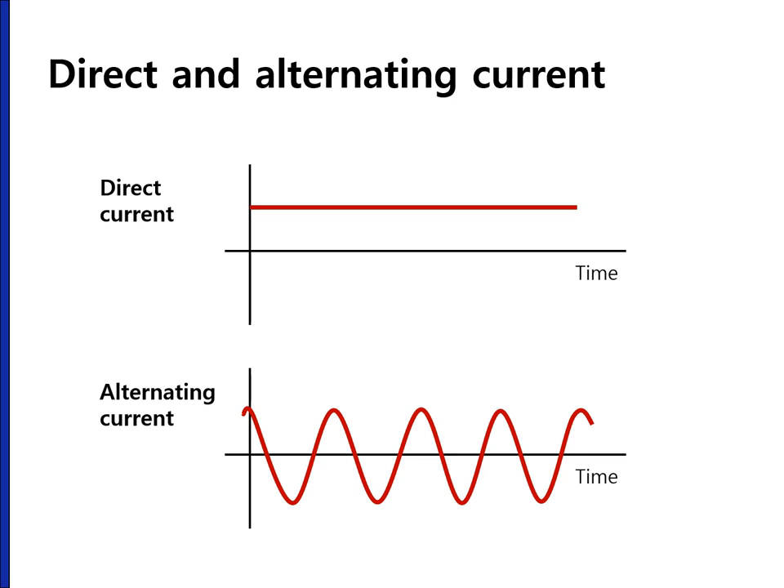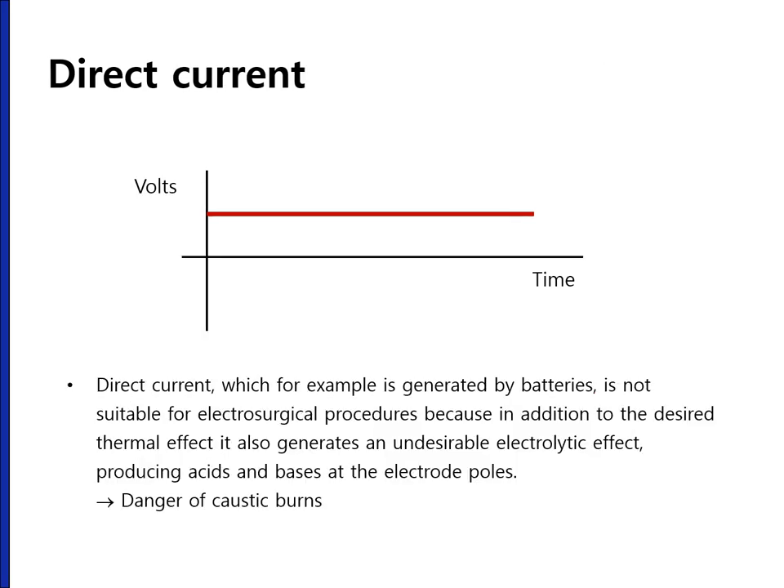There are two types of electric current: direct current and alternating current. Direct current, which is generated by batteries, is not suitable for electrosurgical procedures. In addition to the desired thermal effect, it also generates an undesirable electrolytic effect, producing acid and bases at the electrode poles, which can make caustic burns. We simply don't use direct current in endoscopy.